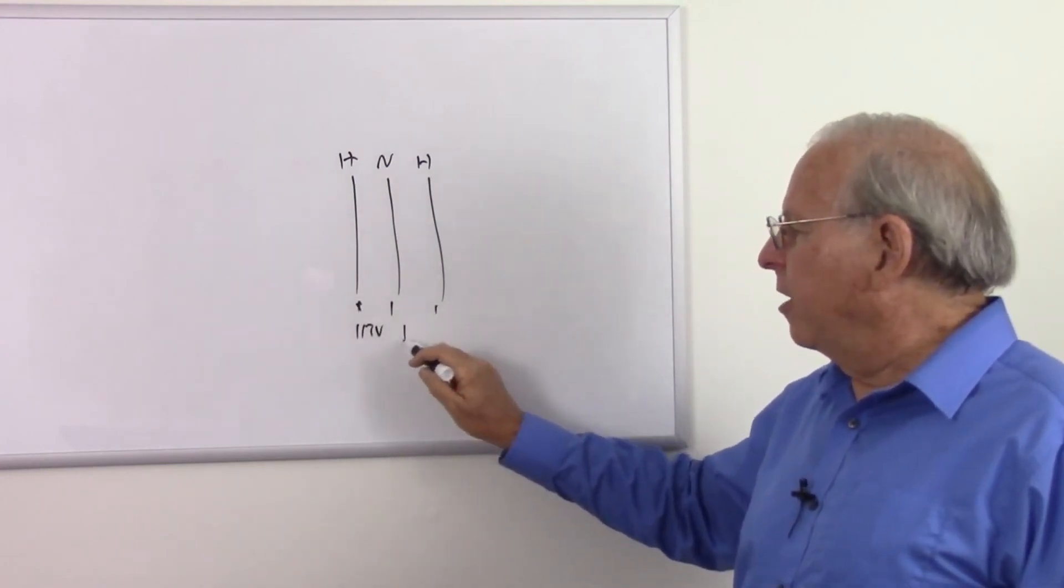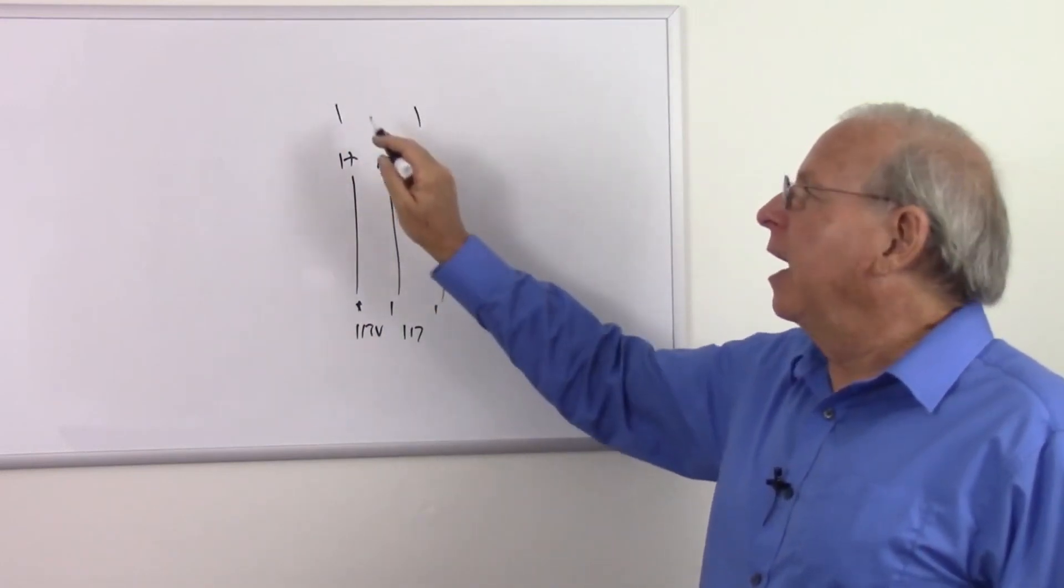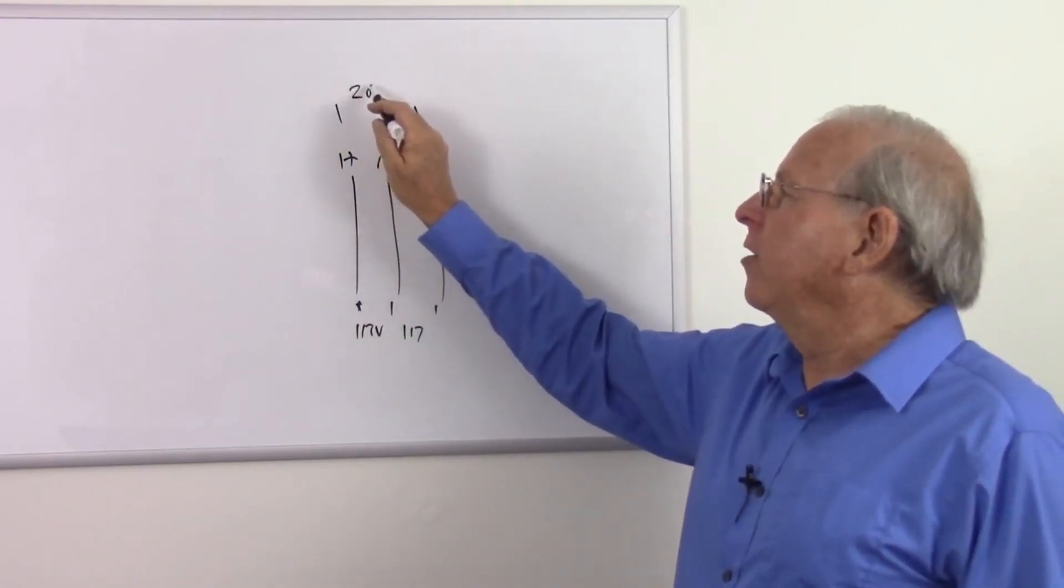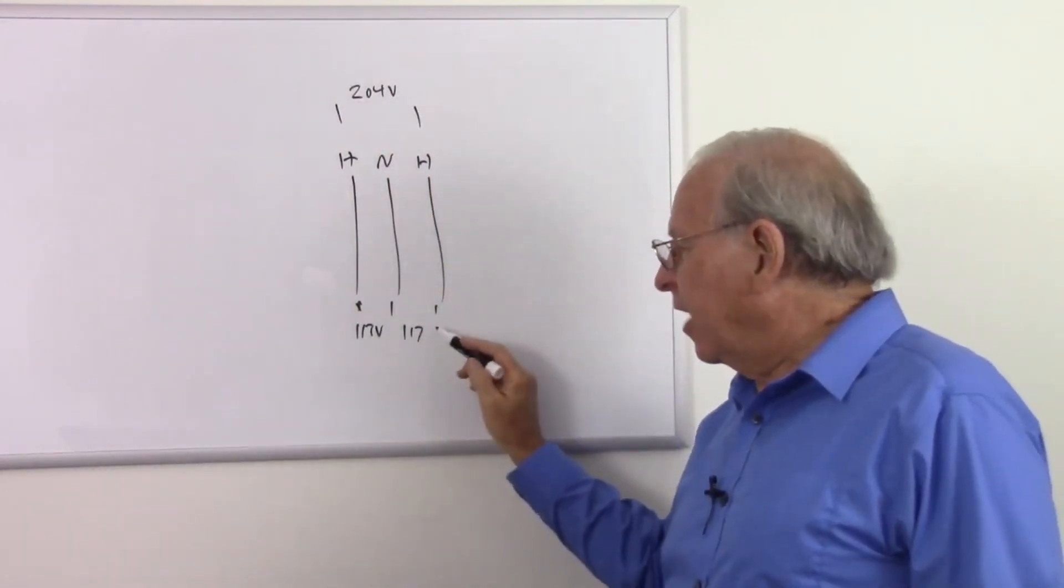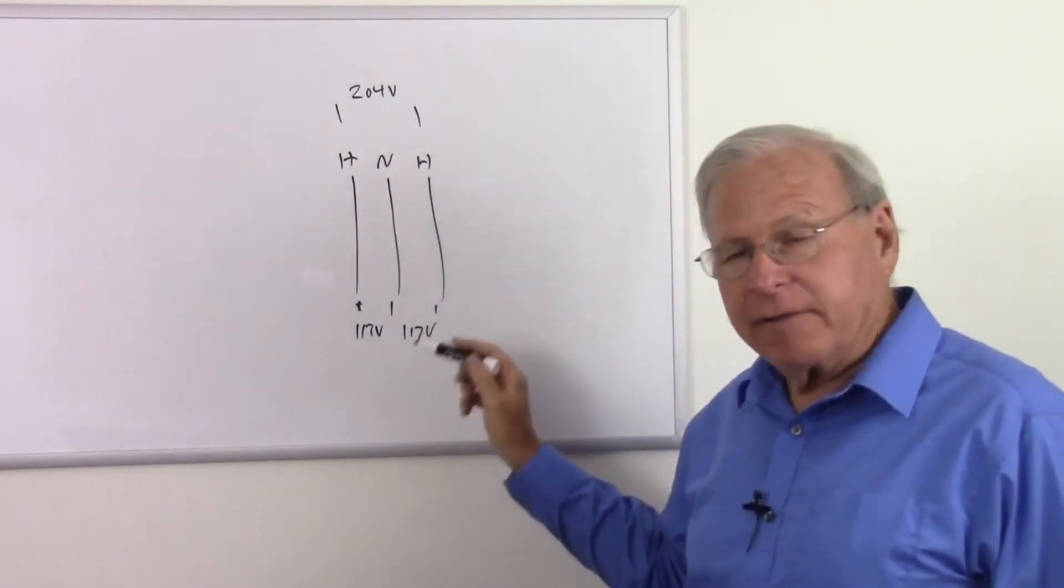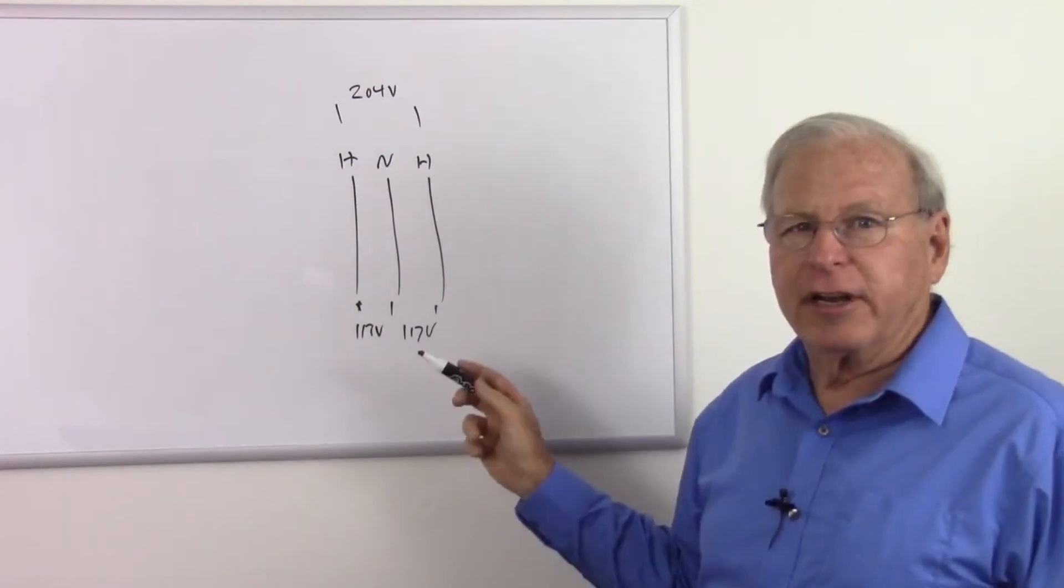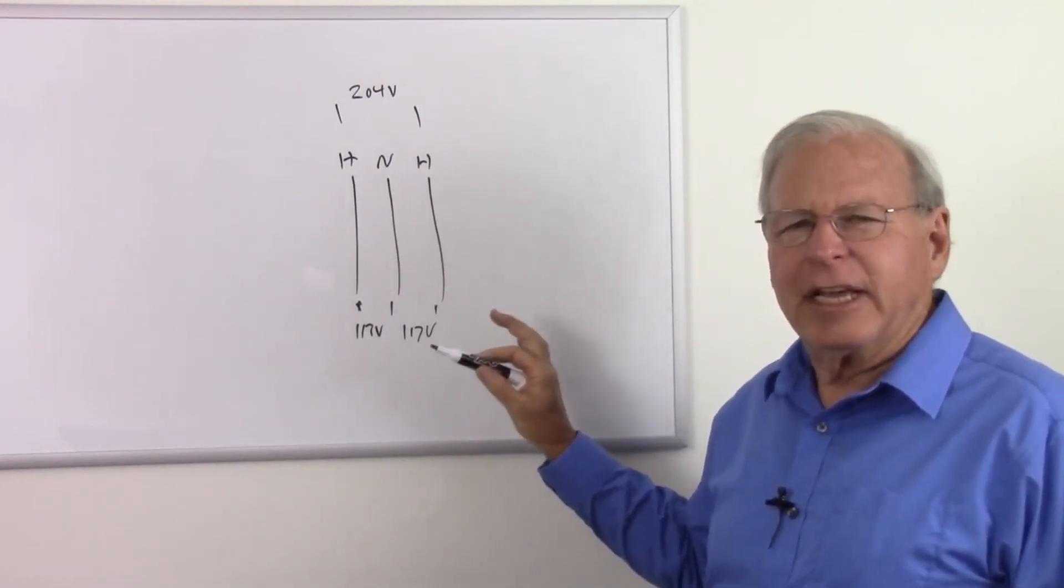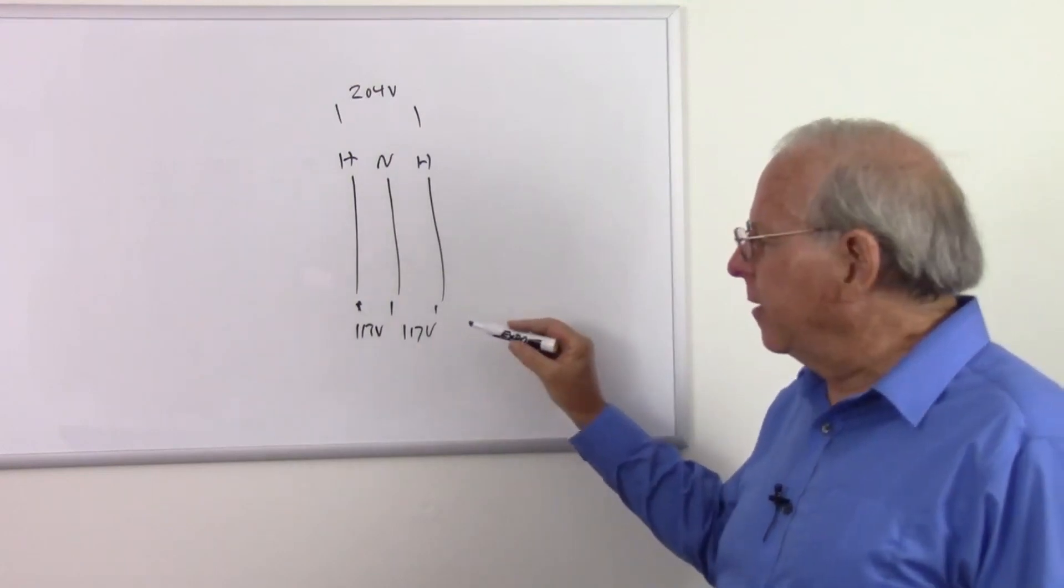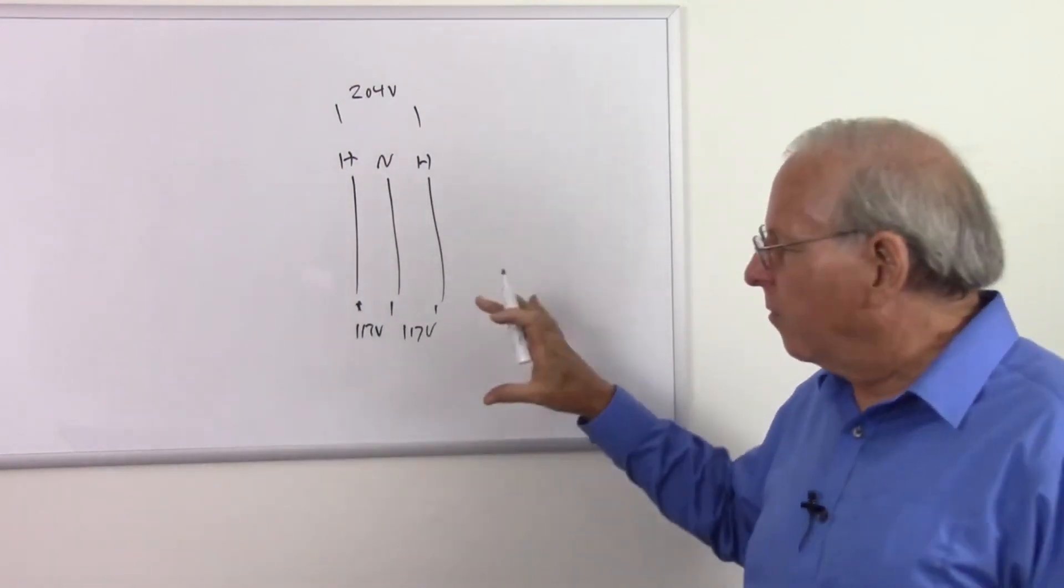And between here and here, I measured 117 volts. But between the two of them, I measured 204 volts. And knowing that this is the standard in the area I live in, 117 volts, that's a standard in a number of areas. They call it 110 or 120. It actually can be anywhere from 110 to 126 volts, I think, and still be within standards.